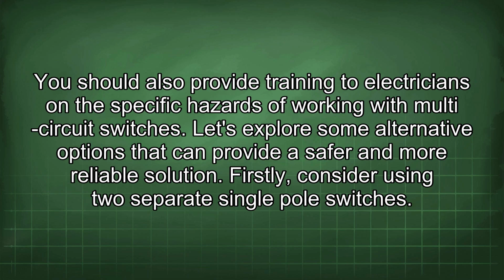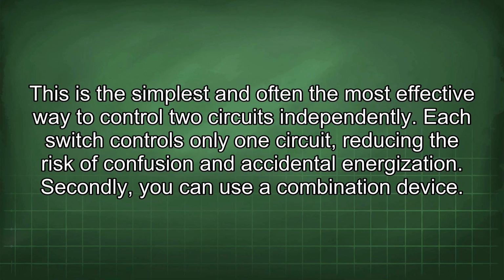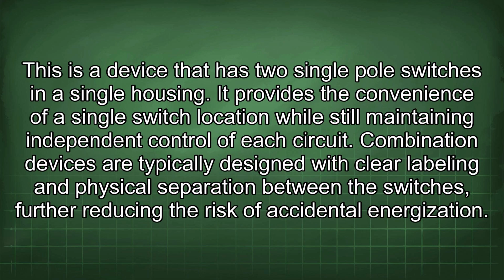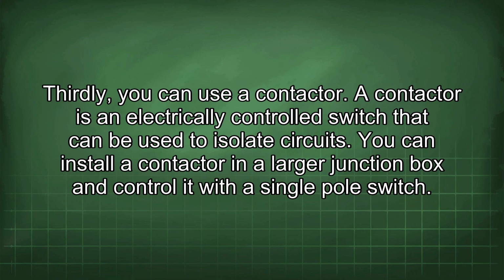Let's explore some alternative options that can provide a safer and more reliable solution. Firstly, consider using two separate single-pole switches. This is the simplest and often the most effective way to control two circuits independently. Each switch controls only one circuit, reducing the risk of confusion and accidental energization. Secondly, you can use a combination device. This is a device that has two single-pole switches in a single housing. It provides the convenience of a single switch location while still maintaining independent control of each circuit. Combination devices are typically designed with clear labeling and physical separation between the switches, further reducing the risk of accidental energization. Thirdly, you can use a contactor.